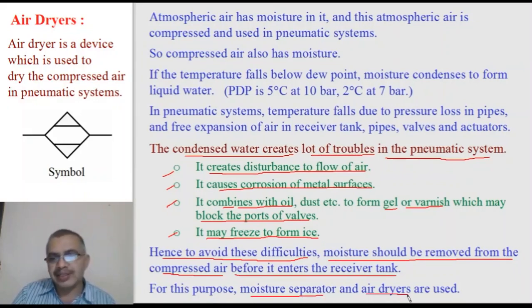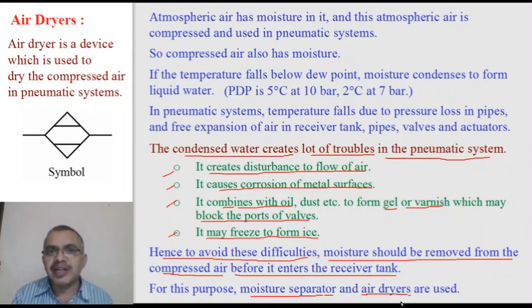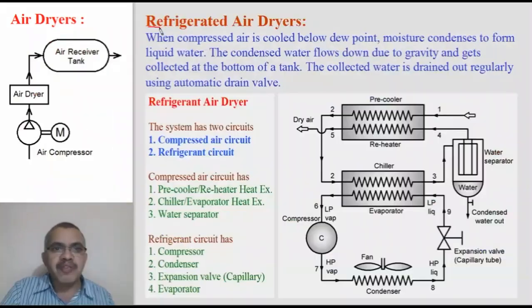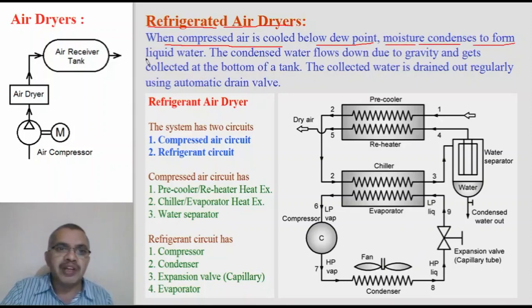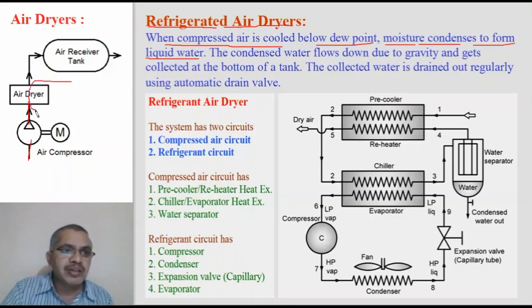To remove moisture from compressed air we use moisture separators and air dryers. There are three important types of air dryers: one is the refrigerated air dryer, the second is the deliquescent air dryer, and the third is the desiccant air dryer. The refrigerated air dryer uses a refrigeration system to cool the compressed air below the pressure dew point, causing moisture to condense into liquid water.